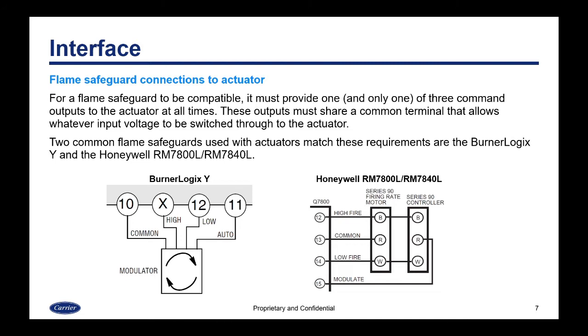Two common flame safeguards used with actuators that match these requirements are the Burner Logix Y from FireEye and the Honeywell 7800L in particular. Here are some wiring diagrams for these, showing the common terminal and the terminals for high, low, and auto going to the modulator. For each of these flame safeguards, the same terminals are available.